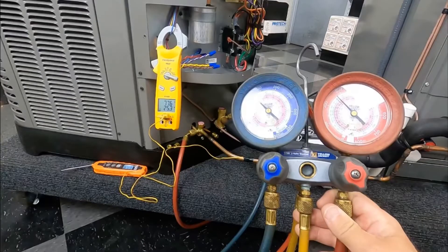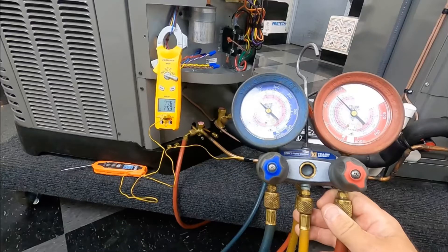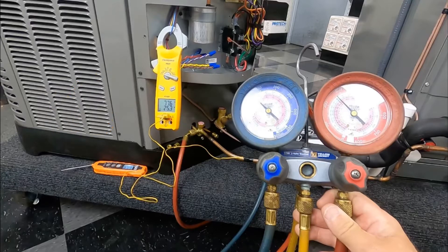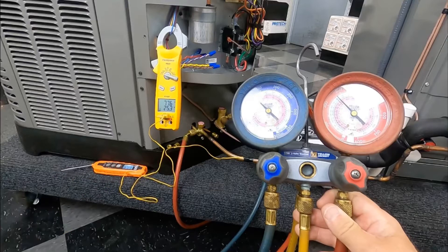Three things we're going to need before we get started. Of course I have a set of gauges here — just some Yellow Jacket analog. You're also going to need something to take a line temp of our liquid line. I've got just a Fieldpiece multimeter with a little thermistor taped to the line there. You're also going to want the outdoor temperature so that we can reference that to our chart and see what our sub-cool needs to be. I just have a little thermometer here taking our outdoor temp.